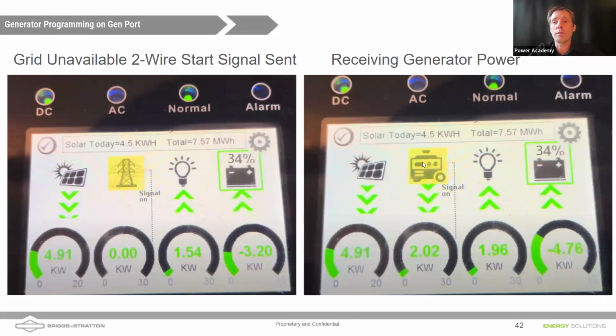Now, there is a qualification period. It's settable. You can set how long you delay before you use that power. I think by default it's 60 seconds, but I'm not certain of that. It might be 100 seconds by default. And now you can see the flow of power out of the generator. I still have solar coming at the same time, right? This is DC solar coming at the same time, and those two things are combining to cover the loads as well as to charge the batteries.